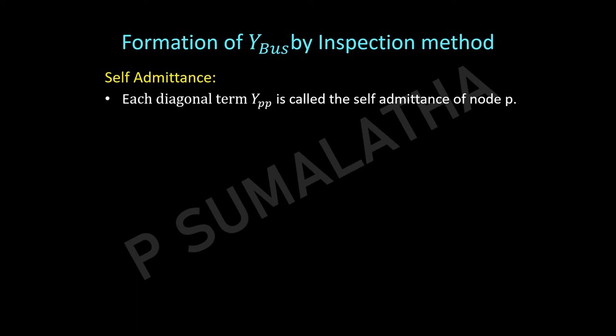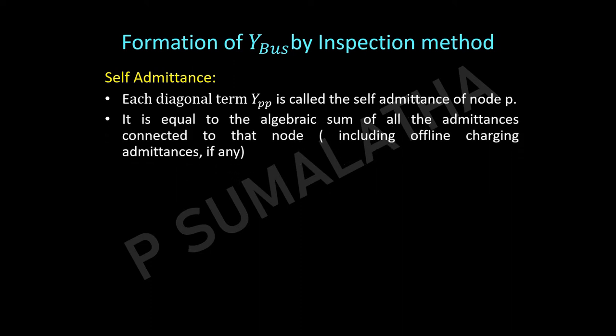The first point is that each diagonal term Y_PP is called the self admittance of node P. If it is Y11 it refers to the self admittance of node 1; if it is Y22 that refers to the self admittance of node 2. In general, P refers to any bus — first, second, or nth bus. The self admittance is obtained by taking the algebraic sum of the admittances connected to that particular node.